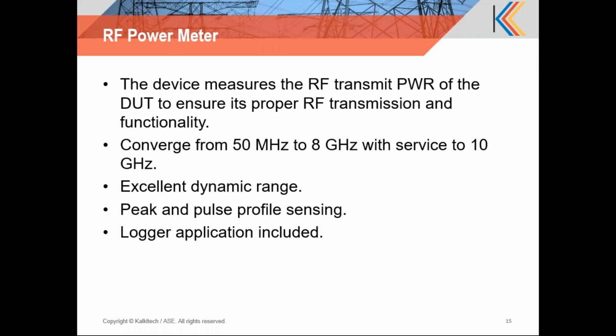Here, for the power meter selection, it can be 50 megahertz to 8 gigahertz, selected upon the requirement. And it should have a good dynamic range. Peak or pulse profile sensing can be done. There are cases in which average sensing or average profile measurement is done for the customer.